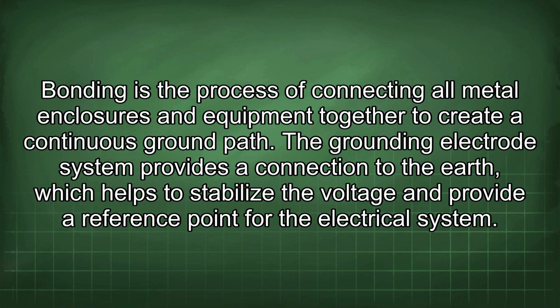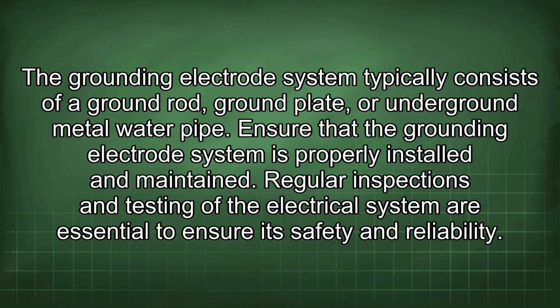The grounding electrode system provides a connection to the earth, which helps to stabilize the voltage and provide a reference point for the electrical system. The grounding electrode system typically consists of a ground rod, ground plate, or underground metal water pipe. Ensure that the grounding electrode system is properly installed and maintained.